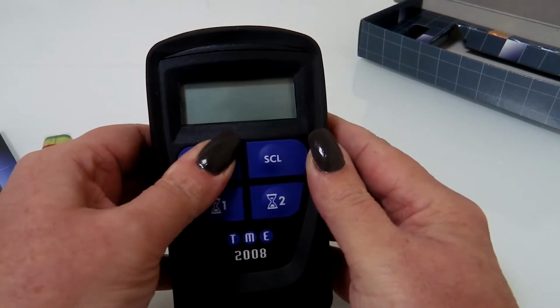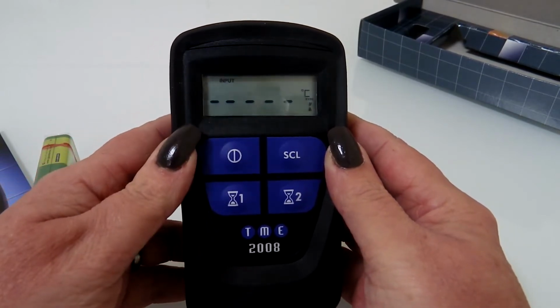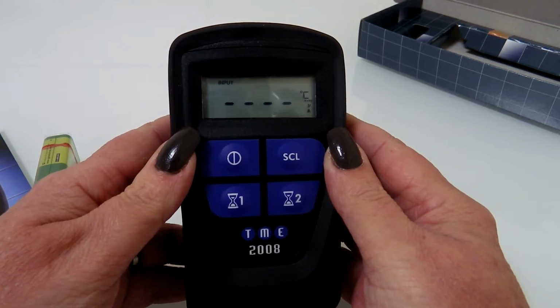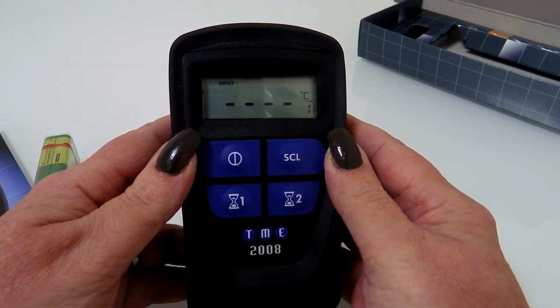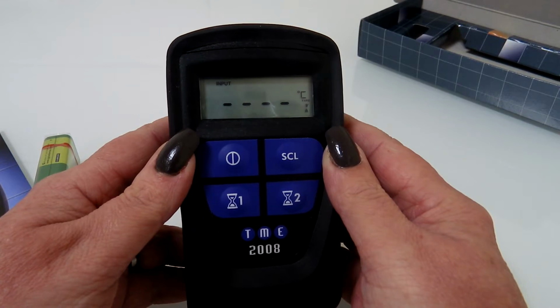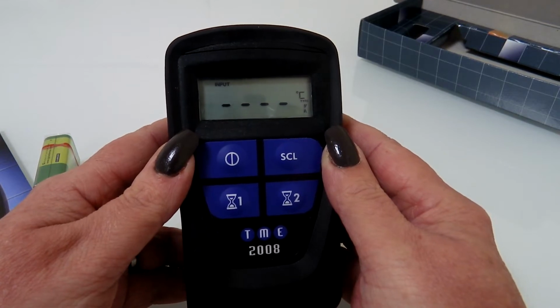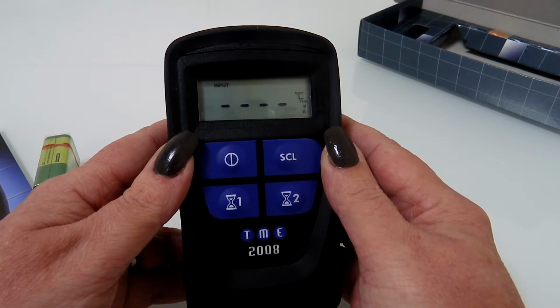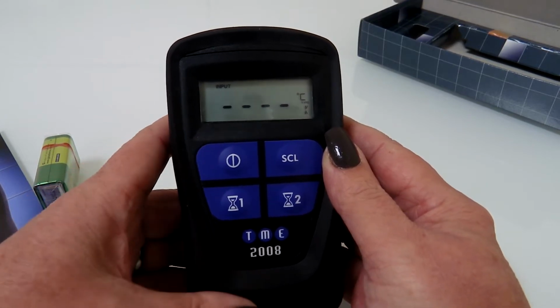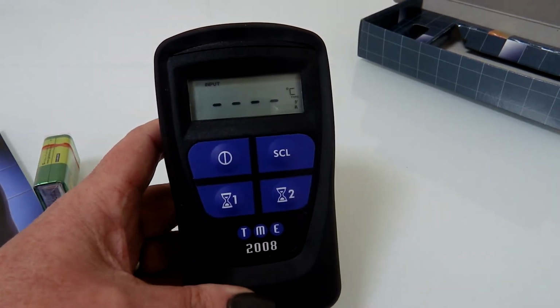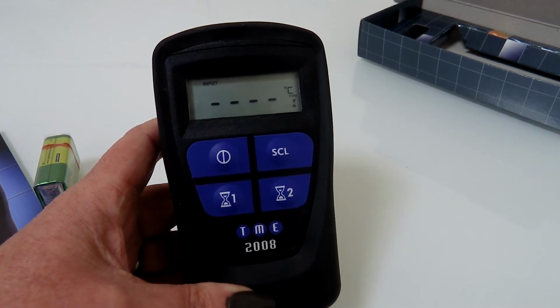Obviously, the first one to go for is the on button. When you first turn on your TME2008, the display will show a series of lines and the word input. This is perfectly normal in this case because we've yet to insert a probe. If, however, you have inserted a probe and your display has not changed, it indicates the probe could be faulty.